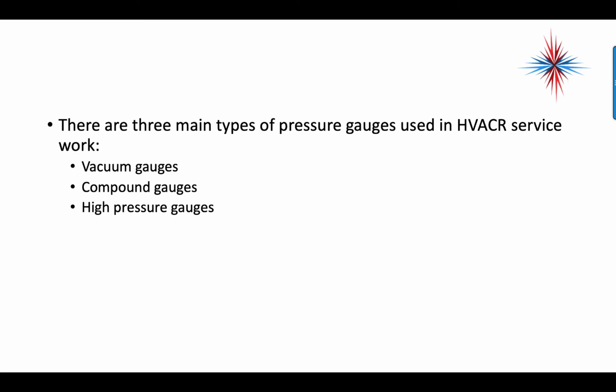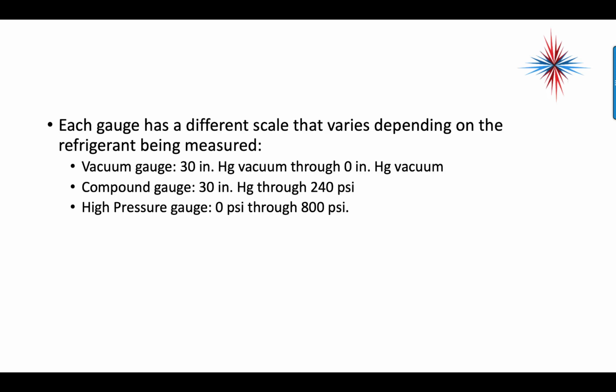There are three main types of pressure gauges used in HVAC service work. You have vacuum gauges, you have compound gauges, and you have high pressure gauges. Each gauge has a different scale that depends on the refrigerant being measured. Vacuum gauges go 30 inches mercury vacuum through 0 inches mercury vacuum. Compound gauge goes 30 inches mercury through 240 psi. In other words, it does both a negative and a positive pressure. High pressure gauge goes 0 through 800 psi. So again, the high pressure side only works over 0.